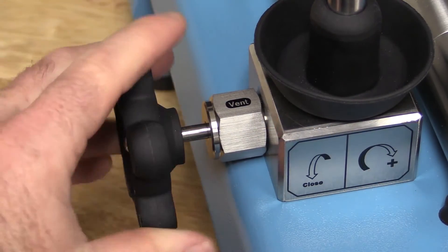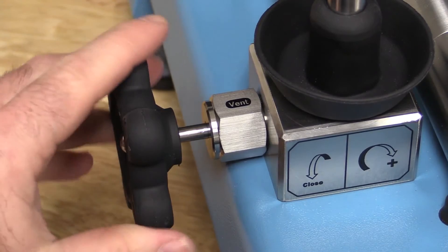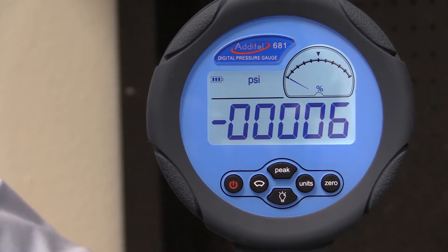Now that we have a vacuum pulled on the system, we will open the vent valve and let the fluid fill into the system. You'll notice this by the gauge settling to zero.